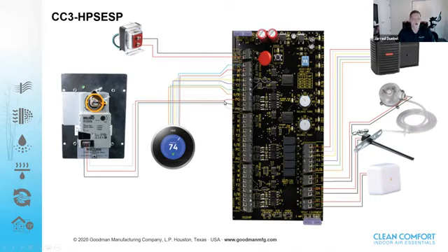However, sometimes technicians call me up and say, hey, we have one of your ESP panels on a truck, and we ran into, maybe it's an old Honeywell system that has 2-wire existing dampers, and the panel has gone bad and we need a replacement panel. Well, you can actually use the ESP panel as a standard zone control panel. You're just not going to install that static pressure sensor. So you can actually use it on 2-wire dampers. When we get into our economy version of our zone control panels, you can use 2 or 3-wire dampers on those as well. But again, you have to have 3-wire dampers and the static pressure sensor installed to use the ESP version.